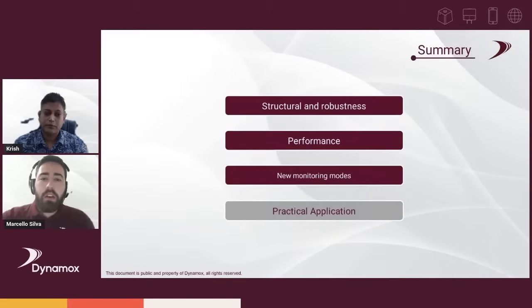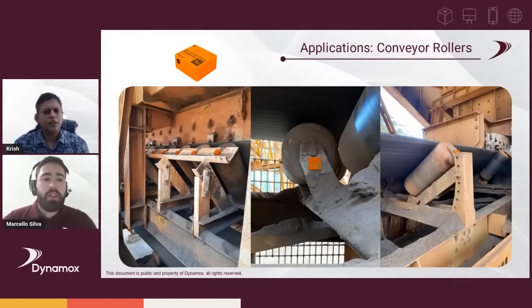Going to some practical applications now, just to give an idea of what we're talking about, so we're not too theoretical. For the TcAg, since this sensor does not perform spectral analysis, what are we talking about? Basically an application like conveyor rollers, where you just stick the sensor and you don't need to know exactly which failure it is. If you see temperature or vibration rising, you'd do a proper inspection, going on field to check for any stuck rollers or dirt causing bad behavior in the asset.